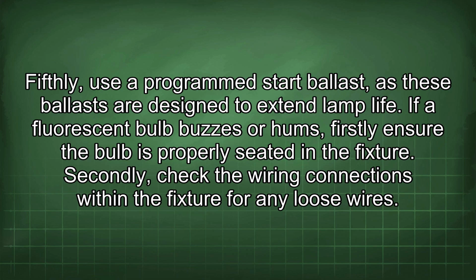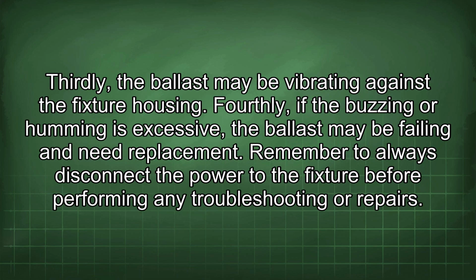If a fluorescent bulb buzzes or hums, firstly ensure the bulb is properly seated in the fixture. Secondly, check the wiring connections within the fixture for any loose wires. Thirdly, the ballast may be vibrating against the fixture housing. Fourthly, if the buzzing or humming is excessive, the ballast may be failing and need replacement.